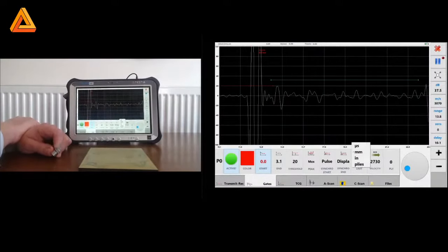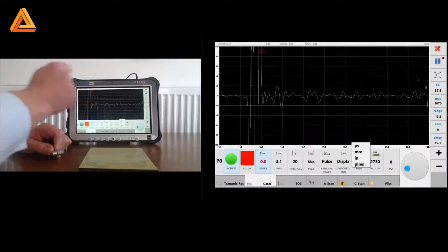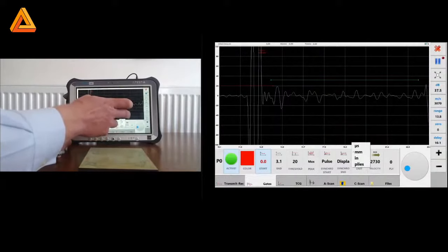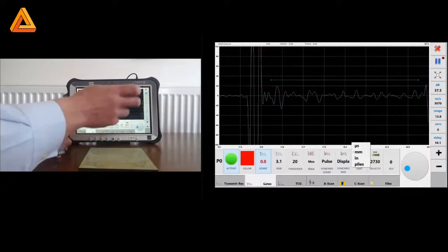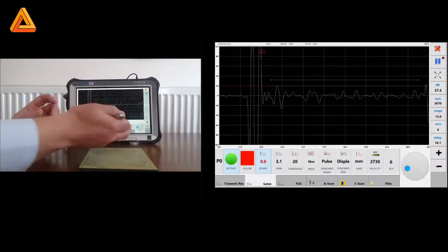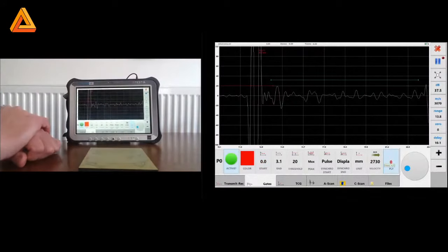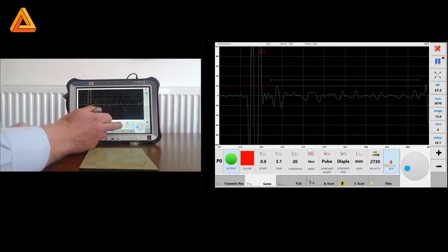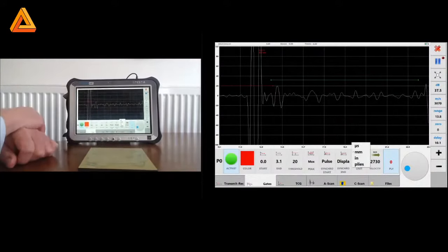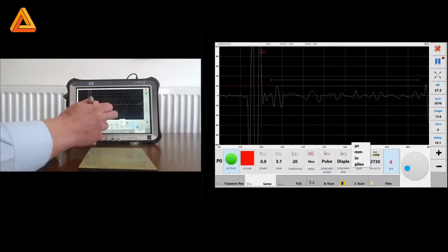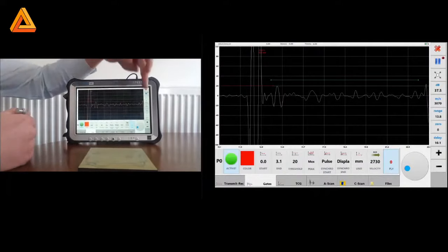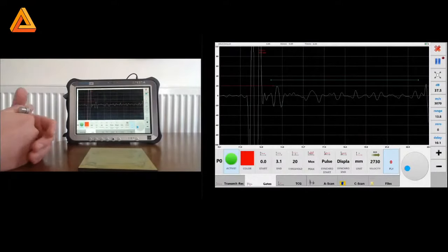Our measurement is a drop-down list and can measure in microseconds, millimeters, inches, or plies. The good thing about the UE1 is that by inputting a ply value here, we can input the depth of plies, thickness of plies, and under the measurement feature, we can then measure in ply depth as well. We'll keep it in millimeters for now. And for each gate, we're able to put an independent velocity against each.